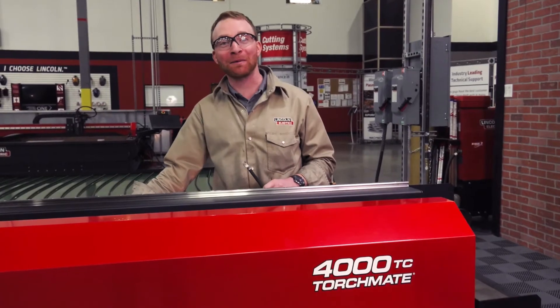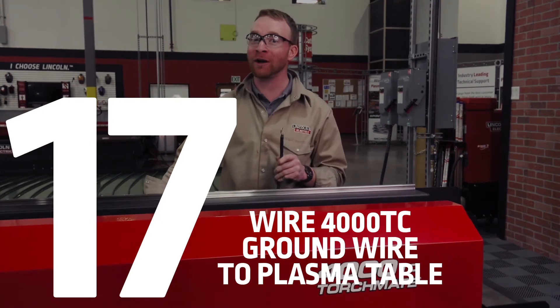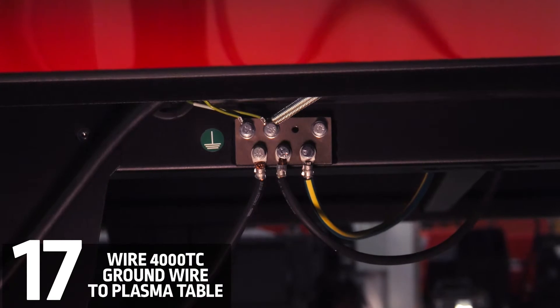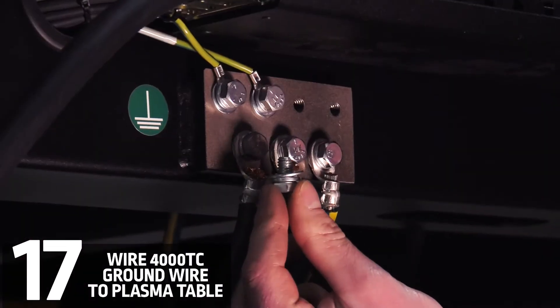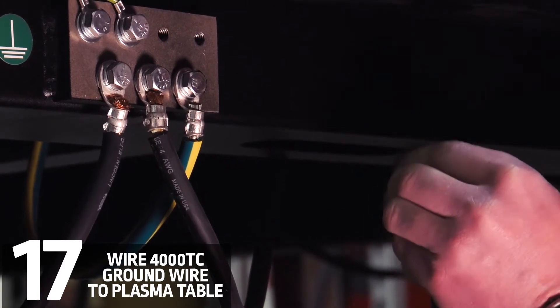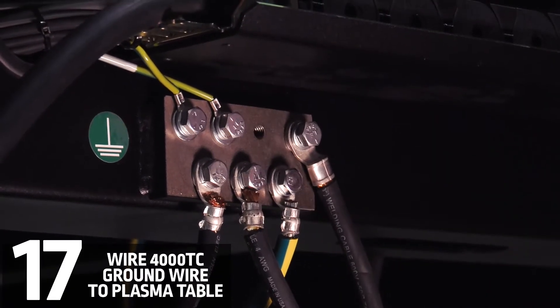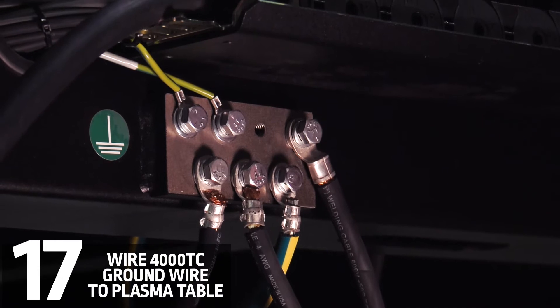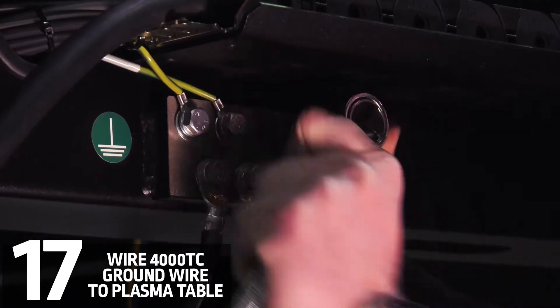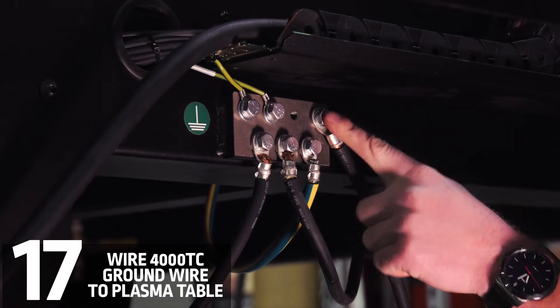Now that we're done underneath the table, we're going to go ahead and find the ground cable coming from the 4000 TC and connect that to the star ground located at the end of the cable carrier rack on the 4400 or 4800. We'll take our 5/16-18 by half-inch bolt and attach it to our ground, then screw it into the star ground. We'll tighten that down with a half-inch socket or a regular wrench — either way works. Don't tighten it too far down; we don't want to mess up any threads in there.